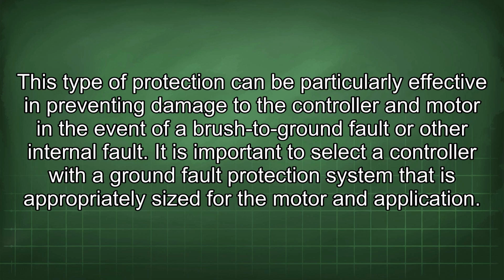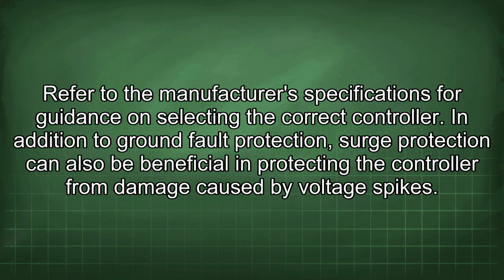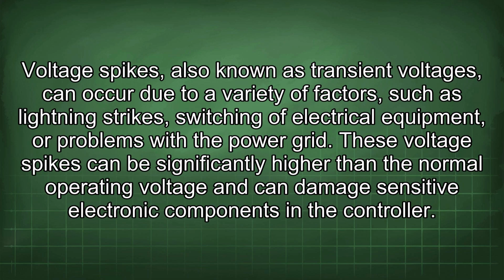It is important to select a controller with a ground fault protection system that is appropriately sized for the motor and application. Refer to the manufacturer's specifications for guidance on selecting the correct controller. In addition to ground fault protection, surge protection can also be beneficial in protecting the controller from damage caused by voltage spikes. Voltage spikes, also known as transient voltages, can occur due to a variety of factors such as lightning strikes, switching of electrical equipment, or problems with the power grid.